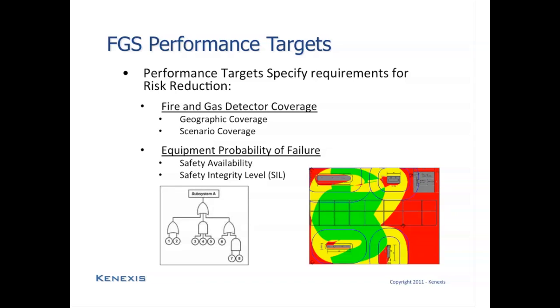And the reason is that the fire and gas coverage would need to be ridiculously high in order for the difference between a SIL 2 and a SIL 3 probability of failure to even be noticed in the overall risk.